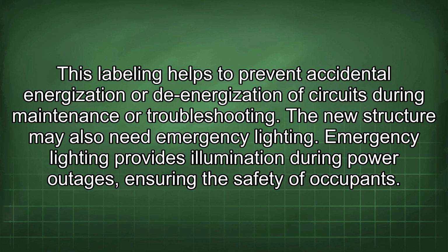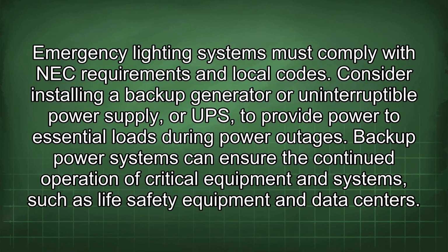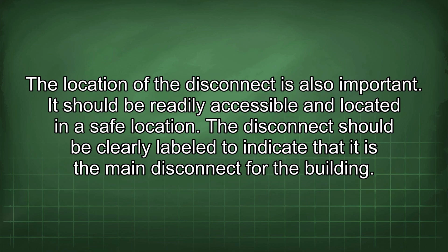The new structure may also need emergency lighting. Emergency lighting provides illumination during power outages, ensuring the safety of occupants. Emergency lighting systems must comply with NEC requirements and local codes. Consider installing a backup generator or uninterruptible power supply, or UPS, to provide power to essential loads during power outages. Backup power systems can ensure the continued operation of critical equipment and systems, such as life safety equipment and data centers.